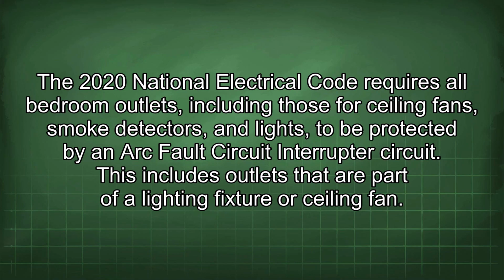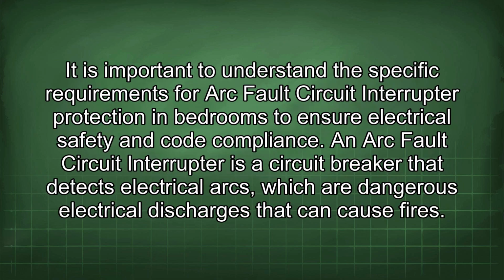The 2020 National Electrical Code requires all bedroom outlets, including those for ceiling fans, smoke detectors, and lights, to be protected by an arc fault circuit interrupter circuit. This includes outlets that are part of a lighting fixture or ceiling fan. It is important to understand the specific requirements for arc fault circuit interrupter protection in bedrooms to ensure electrical safety and code compliance.